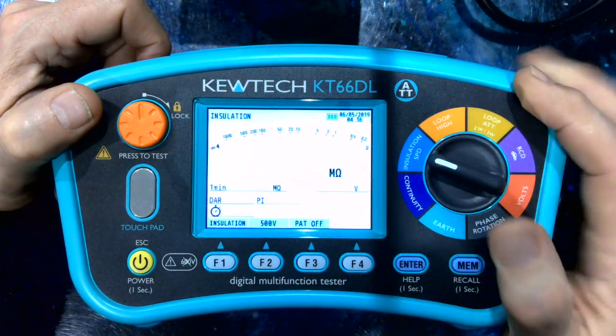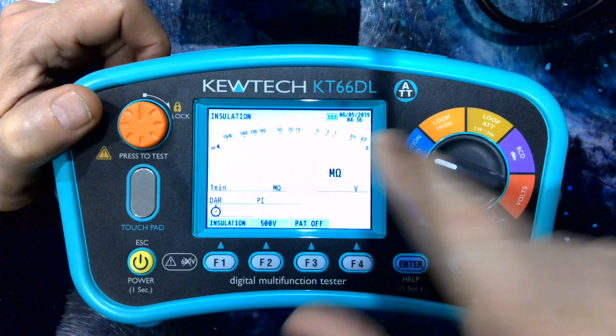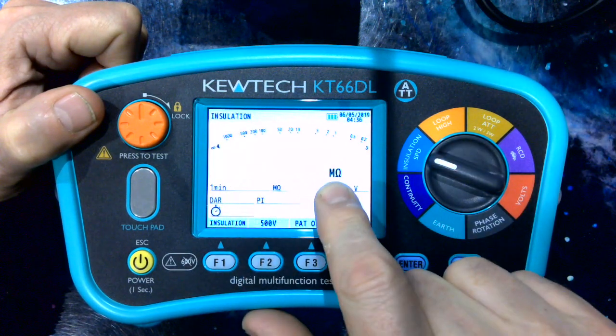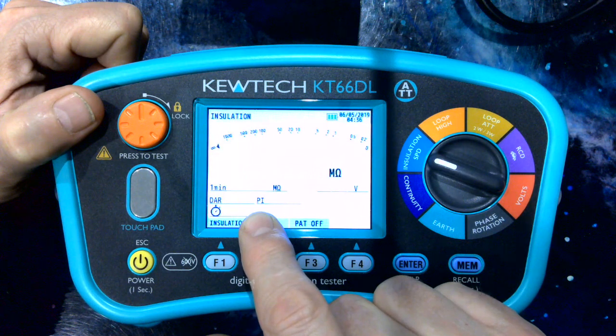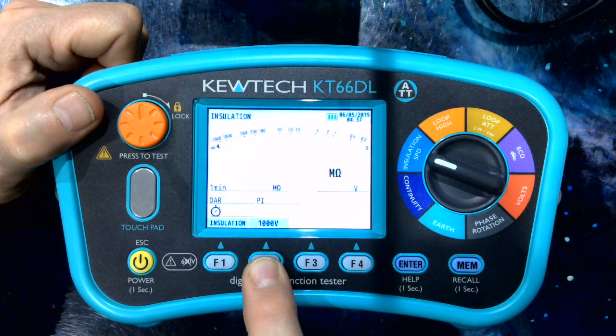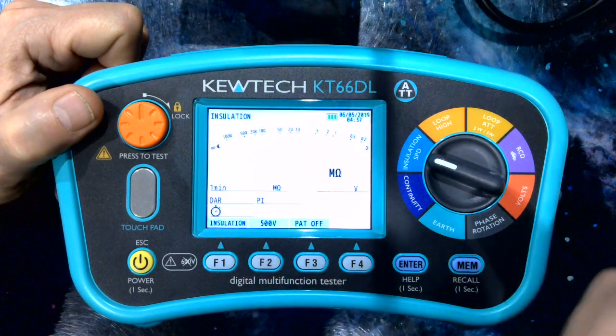Moving on to insulation. Here we can see the benefit of the dot matrix screen — it gives you a digital bar graph of how the insulation is testing. Test results come here, and you also have the opportunity to do a DAR and your polarization index. We have a range from 100, 250, 500 and 1000. For PAT testing, you've only got 250 and 500 in line with the standard.